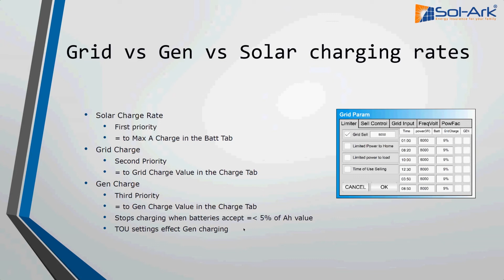And also, if you're using a generator and time of use at the same time, please note that the time of use settings do have an effect on generator charging. Namely, this column on the right here with a bunch of checkboxes for a generator. If you do not have a checkbox in the current time slot, whenever the generator is called for, we won't call for the generator. Basically, the reason for this is you can have quiet time for the client. So if they don't want the generator on, if it's noisy or something, it's by the bedroom or what have you, you can have slots where the generator just won't be called for. Or you can use it to stagger how long the generator can run for, and a few other things like that. But just be aware of that whenever you're setting up time of use with a generator.